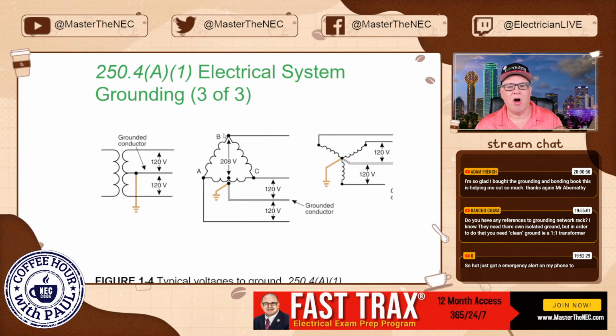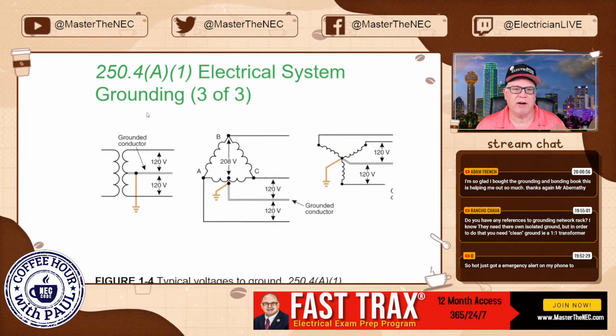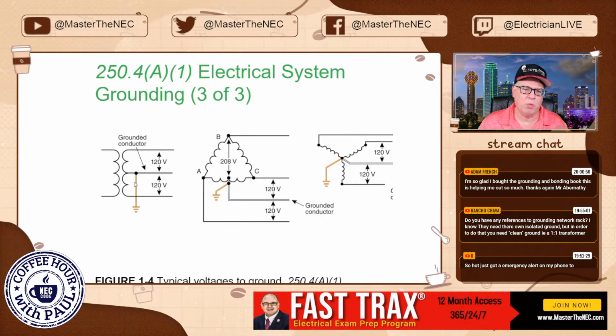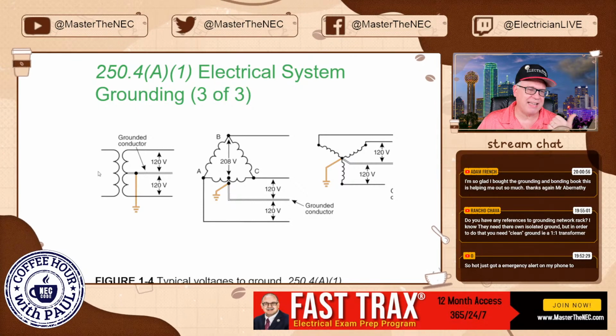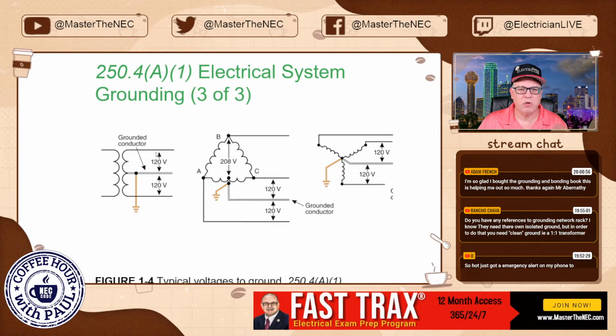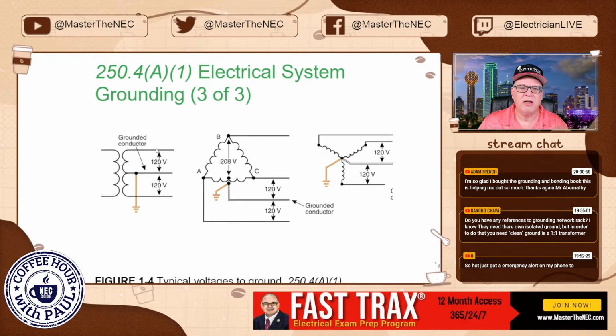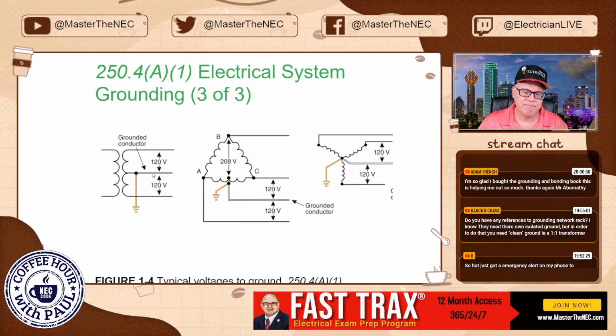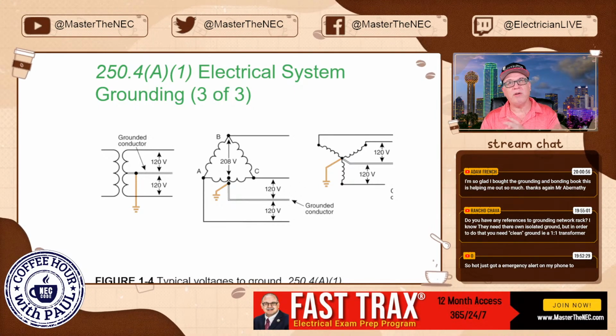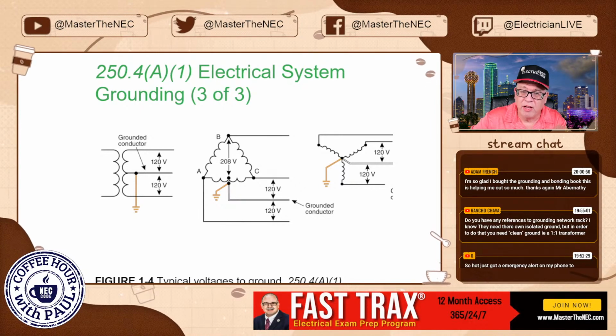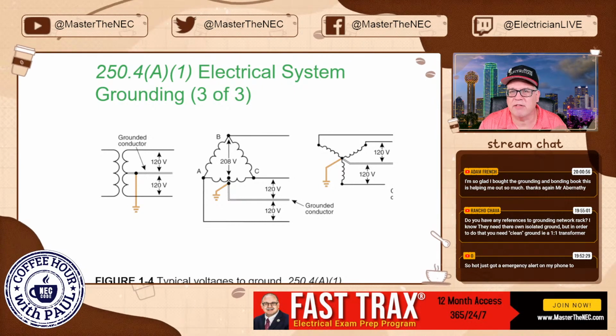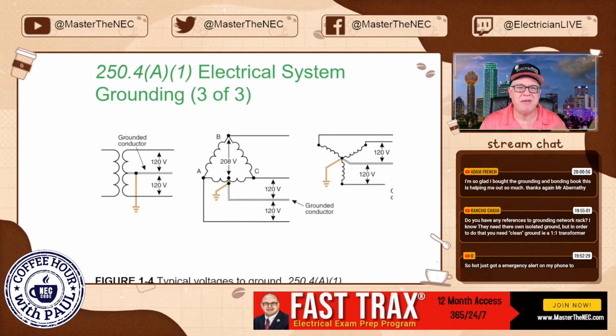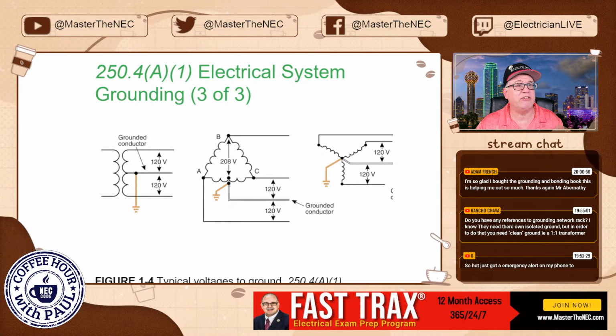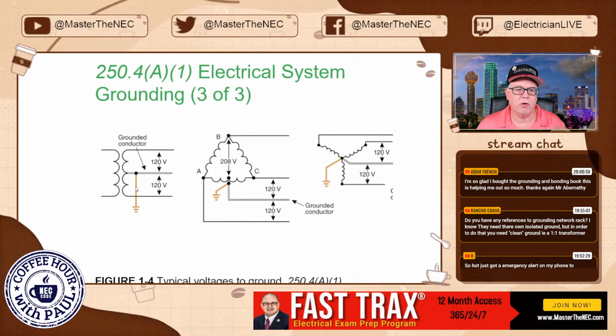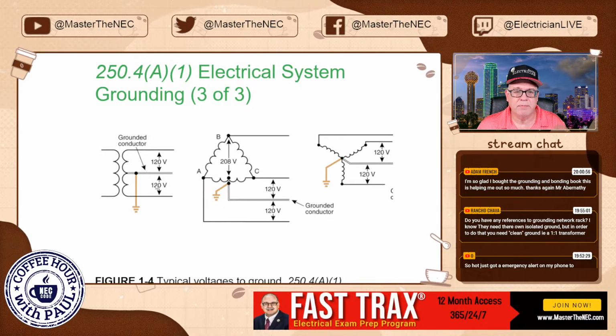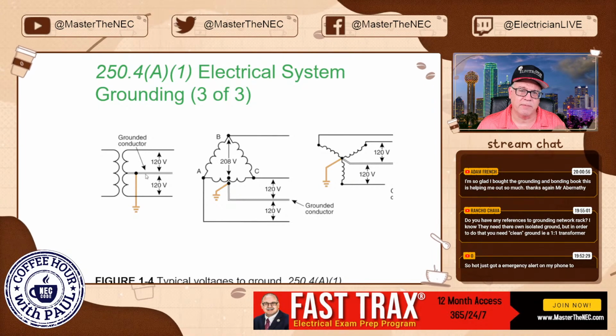All right, here are examples of grounding systems where these are grounded. Here's a typical one like we might see here. You have a transformer, like the one you saw, 7200, and here we have the secondary, utility based. This is a grounded conductor. Now, you don't always have a grounded conductor, I mean, you don't always have a neutral. But anytime you have one of the conductors connected directly to the earth, then you do have a grounded conductor. It's not through any impedance device, so it's not a high impedance ground. It's a direct connection to earth, through a grounding electrode conductor to an electrode. In this case right here, there's a connection. So this is the grounded conductor. But check this out.